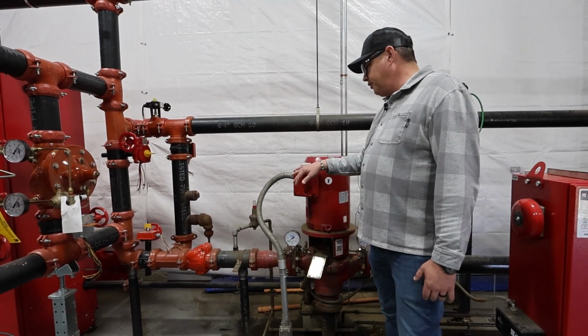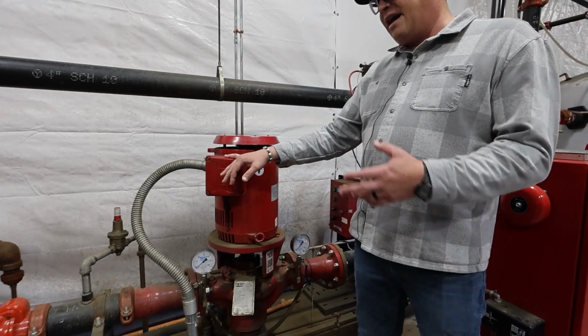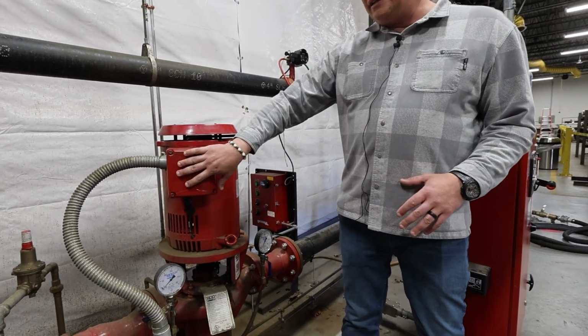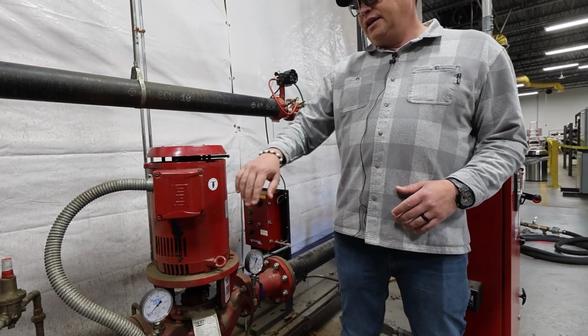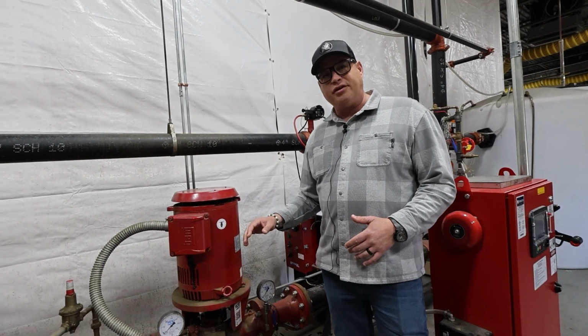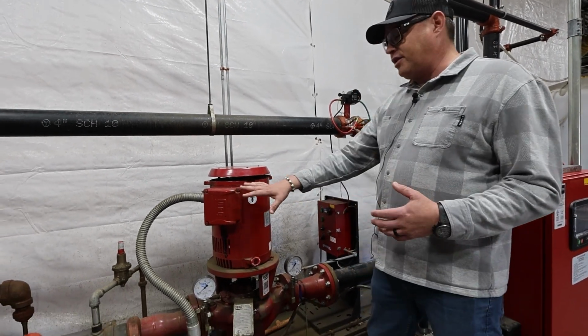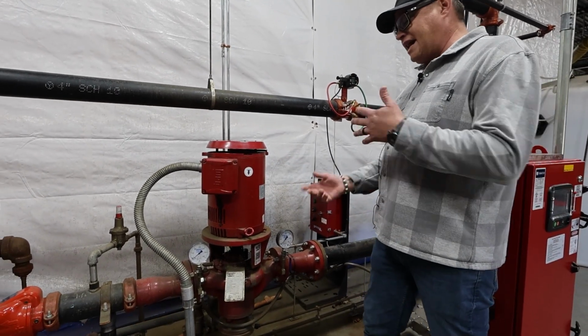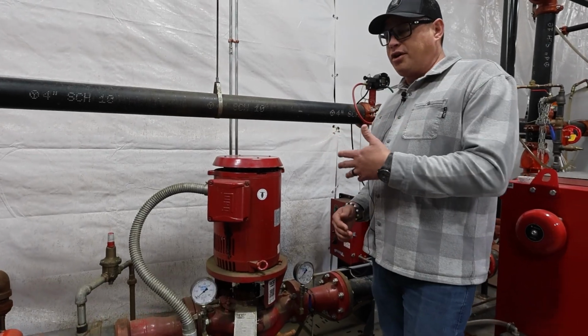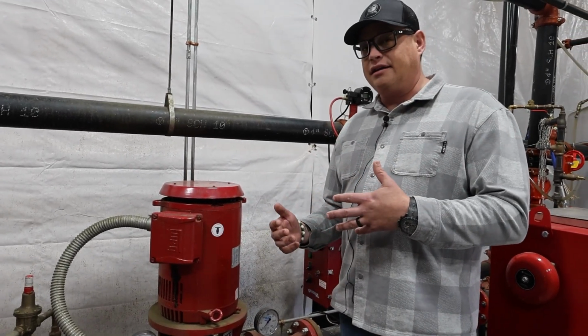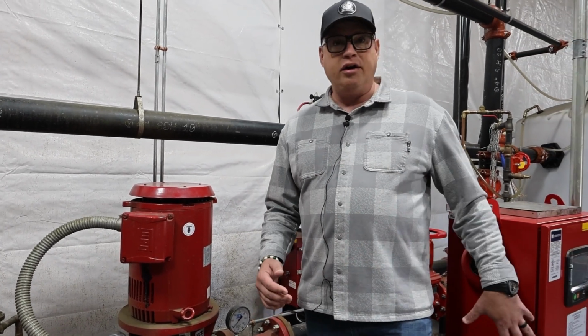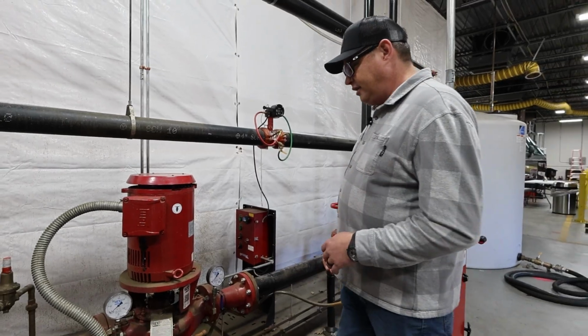Typically, if it's a brand new setup and I've never touched the pump before, I like to take the terminal box cover off and just check the lines, make sure that it's wired up properly, make sure that the right connections are in place. Because the last thing I want to do is start a pump that is wired incorrectly and could potentially arc and cause harm to myself.